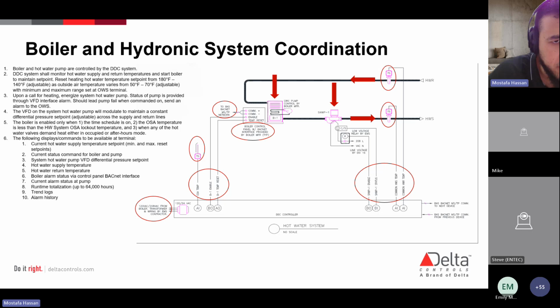So reset the heating hot water temperature set points from this range, okay, as the outside air temperature varies from this range. Upon a call for heating, energize the system hot water pump. Again, there's your system hot water pump. The status of the pump is provided through the VFD interface alarm. So there must be a VFD for this pump, and we're going to run another communication point to that VFD and collect information on that pump, whether it's on, whether it's having a fault, what the speed of the pump is, and then also if the pump is in fail mode, right? There's something wrong, that's going to send an alarm to the workstation.